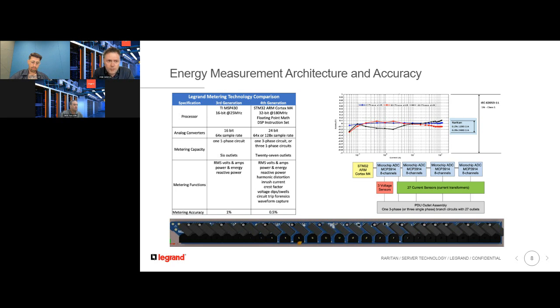A 3-phase 54 outlet PDU model only requires 2 of these relay boards, and the 2 metering chips on these boards are able to provide in total over 740 electrical measurement data samples every second. That's why, as I mentioned earlier, it's also important to intelligently filter this data and only provide relevant data on demand.